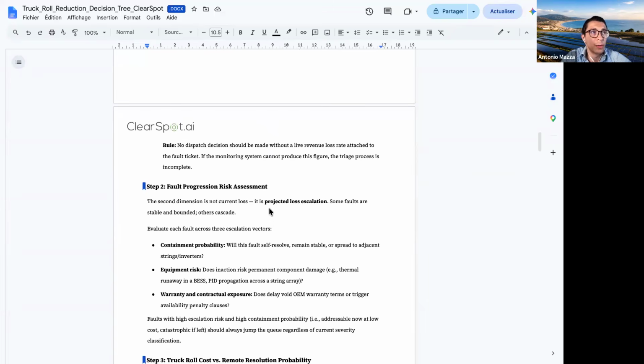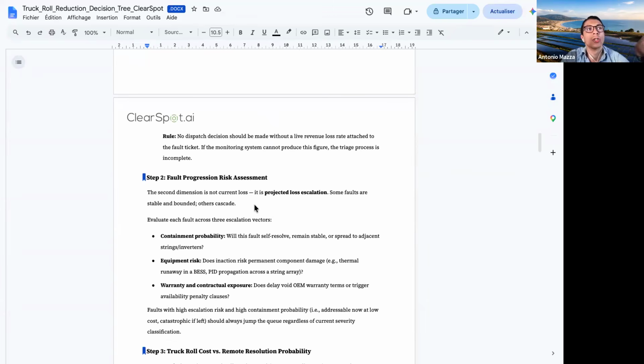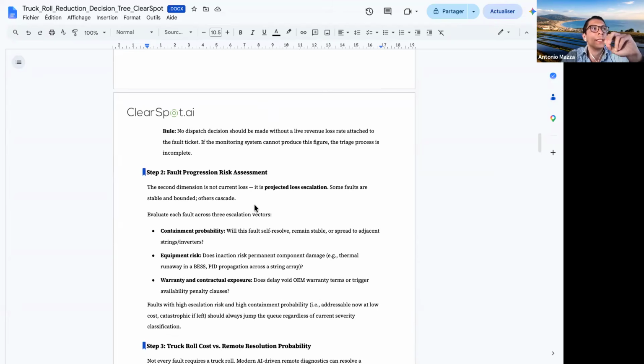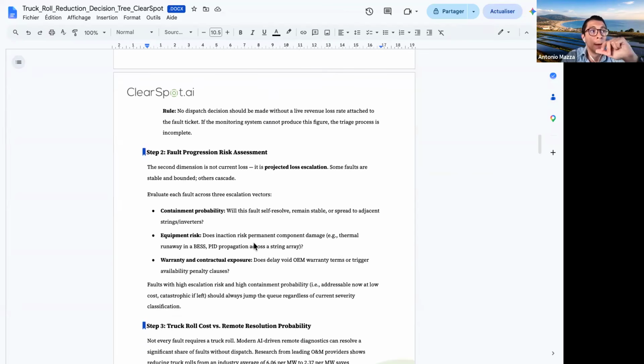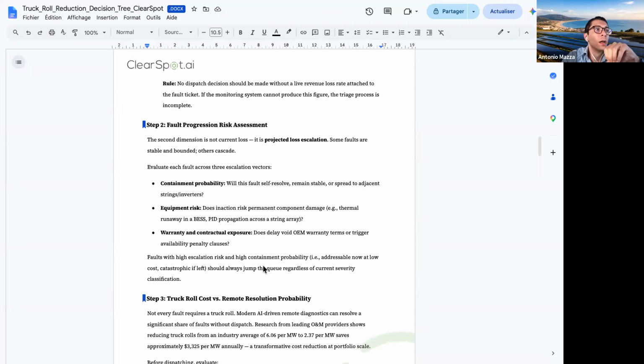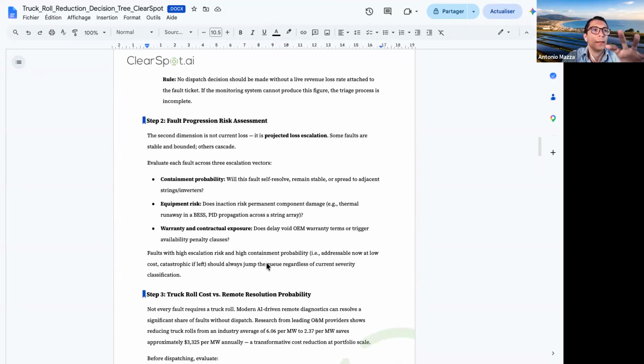The fault progression risk assessment, the second dimension, is not current loss but projected loss escalation, because some faults, we know, could be stable and bounded, while others can cascade. So evaluate containment probability. Will this fault self-resolve, remain stable, or spread to an adjacent string or inverter? Equipment risk: does inaction risk permanent component damage, thermal runaway, PID propagation on a string array? Warranty and contractual exposure: does the delay void OEM warranty terms or trigger availability penalty clauses? So faults with high escalation risk and high containment probability, addressable now at low cost, should always jump the queue regardless of the current severity classification.